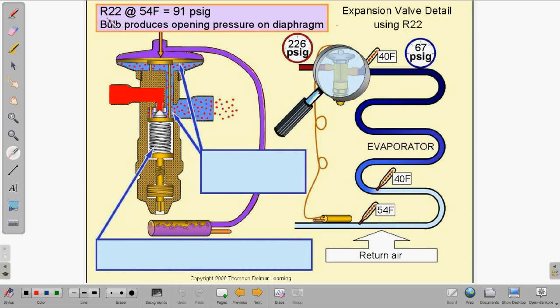So, for example, in this example, we have R22 refrigerant at 54 degrees. Now, you see right here, this sensing bulb is mounted to the outlet of the evaporator, and if you put your thermometer on there, it's 54 degrees. So, using the pressure temperature chart, you can cross that over from 54 degrees is 91 pounds per square inch of opening pressure on the top of the TXV valve. And that's going to start pushing that diaphragm down. It's going to open up this valve seat right here, and it's going to start to allow that refrigerant to flow through the valve seat and out into the evaporator. So that's not the only pressure, otherwise it's going to push this valve open as far as the design will allow and just flood the evaporator. We don't want that to happen.